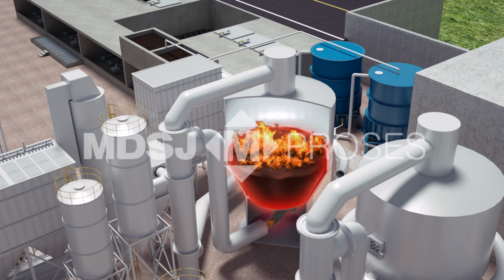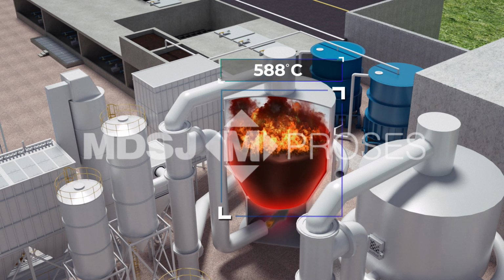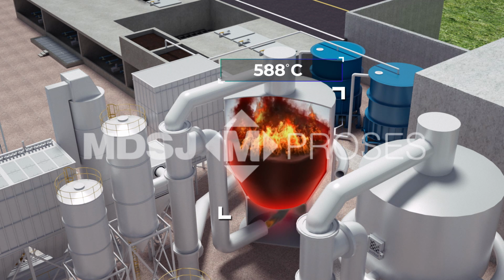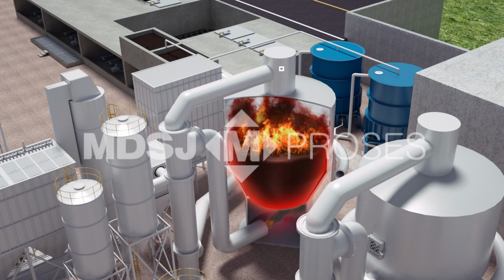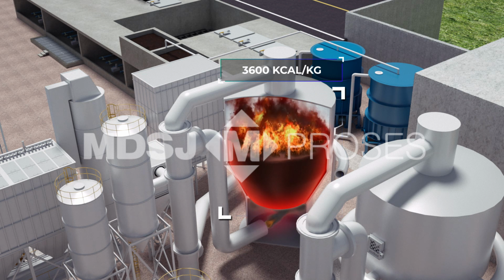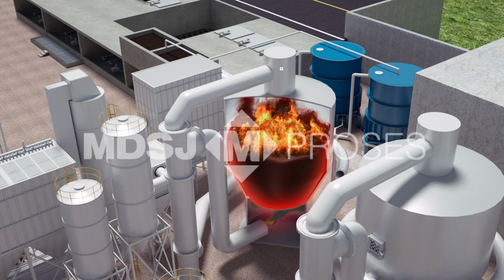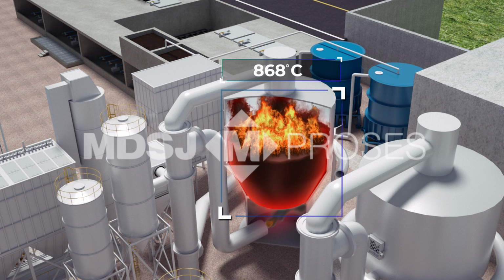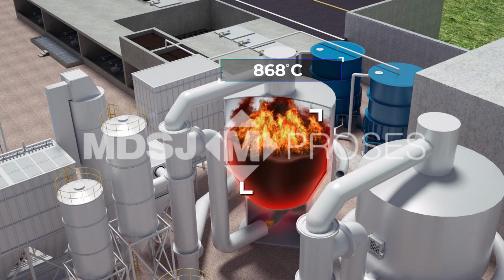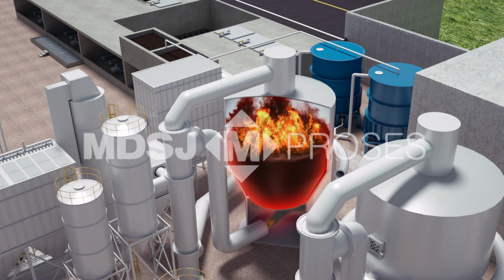Air from the fluidizing air blower is heated up to 588 degrees Celsius by a preheat heat exchanger and primary heat exchanger utilizing heat from the flue gas. The hot air is sent to the incinerator for combustion and fluidizing the sand bed. The sludge, with a 3,600 kilocalorie per kilogram heat value, mixes with this hot fluidized sand bed and combustion air, is burned completely in 5 seconds at 868 degrees Celsius and is converted into inert ash and flue gas.